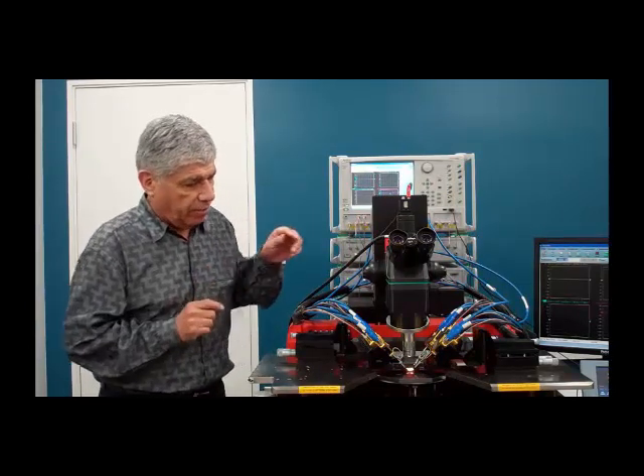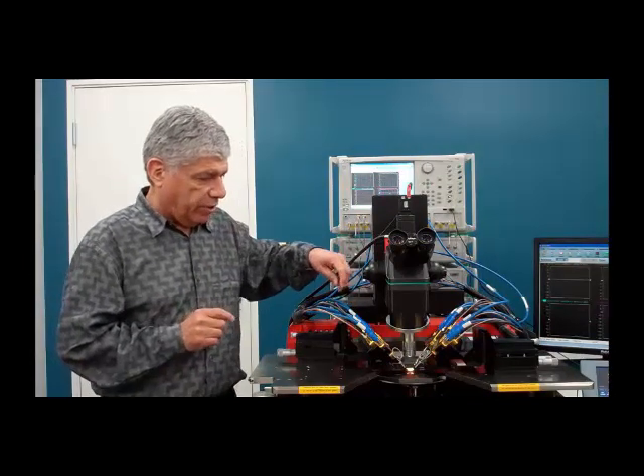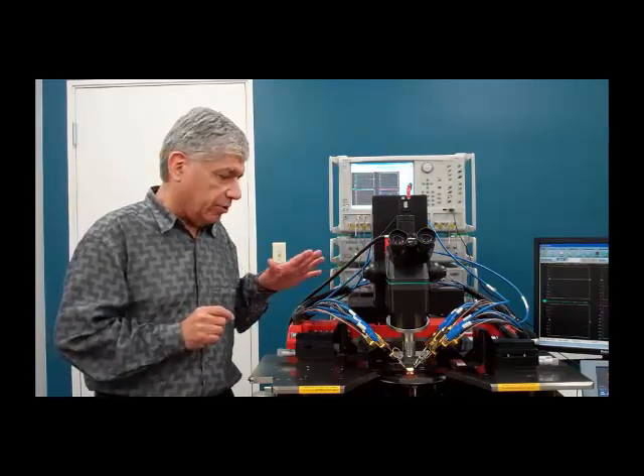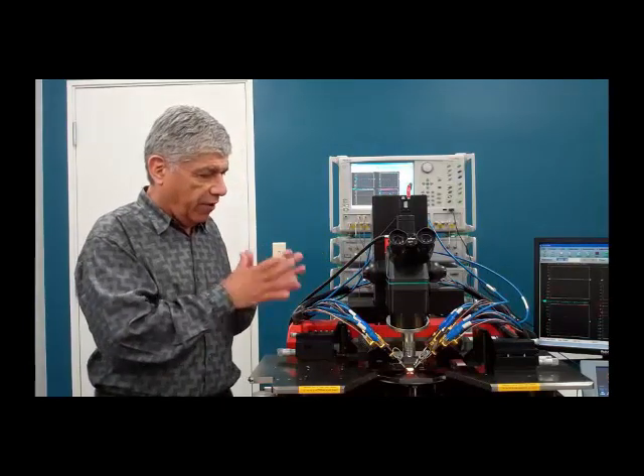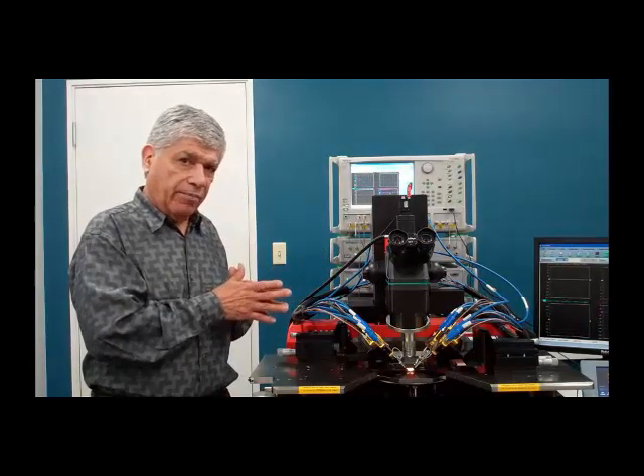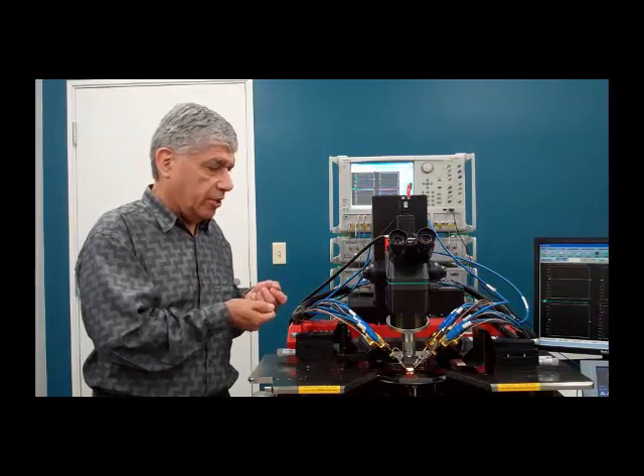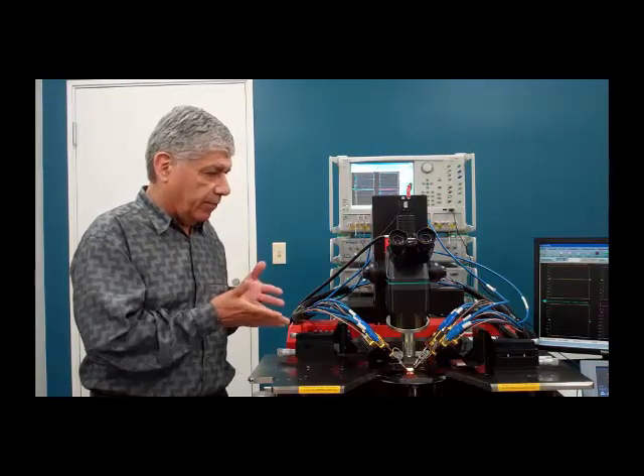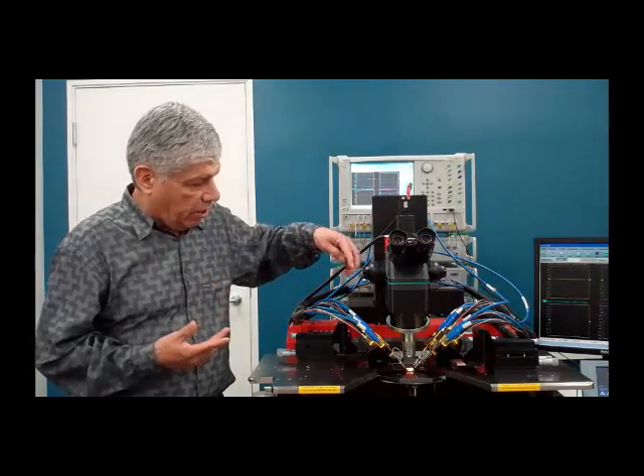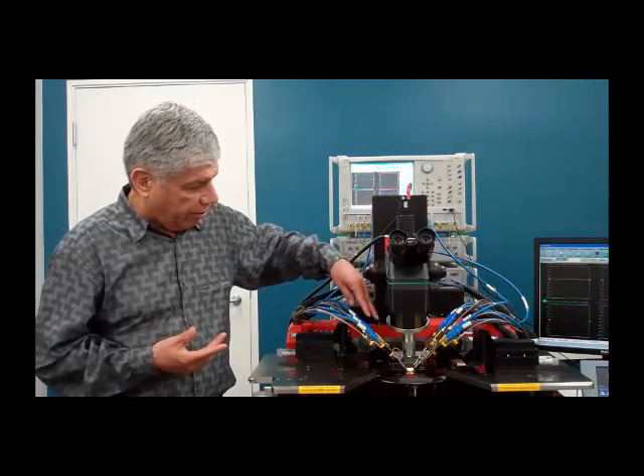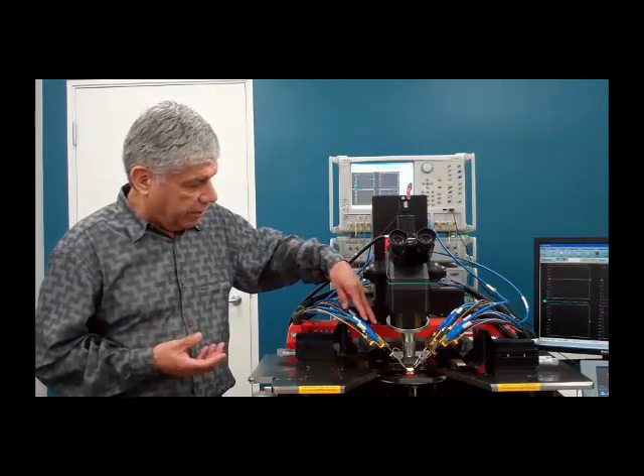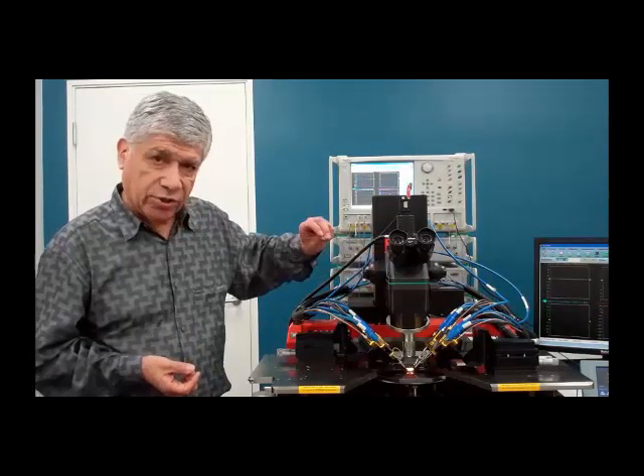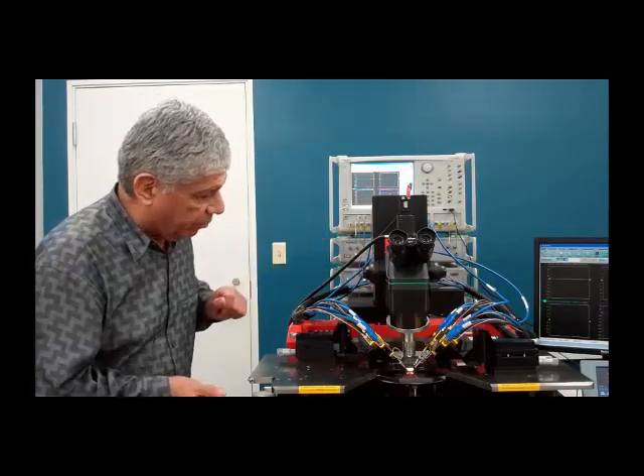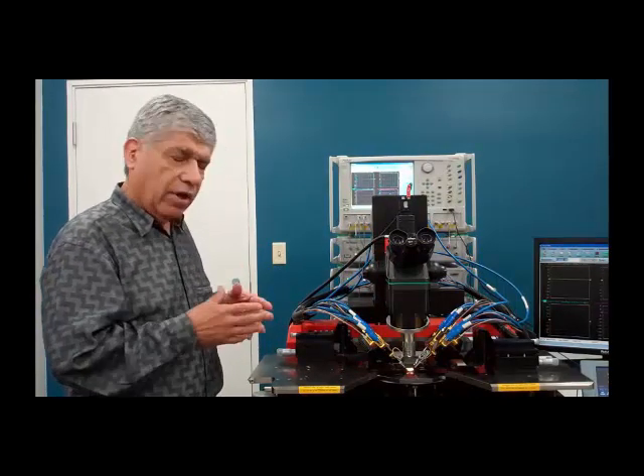So as I was mentioning, the modules are developed by Anritsu. They're nonlinear transmission line modules, and they are very compact in size, so that it makes installation on a probe station very easy and convenient. You can see that we have 4 modules connected on our Anritsu brackets that are connected then to the differential probes. In this case, the probes are the GGB probes operating to 145 with a 0.8 millimeter connector.